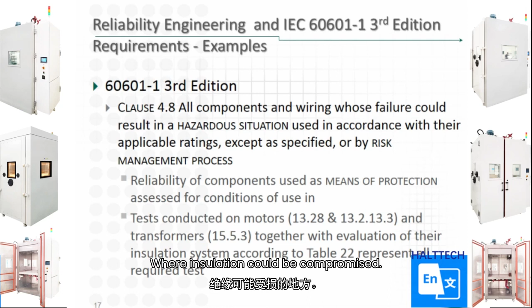Other examples of 60601 and how it plays into the reliability engineering discipline. Clause 4.9 talks about components with high integrity characteristics, provided because a fault in a particular component can generate an unacceptable risk. These are the types of components where a failure really can't be allowed. A failure of any of these high integrity components would result in an unacceptable risk to the patient. In other words, if it fails, somebody's going to get hurt.